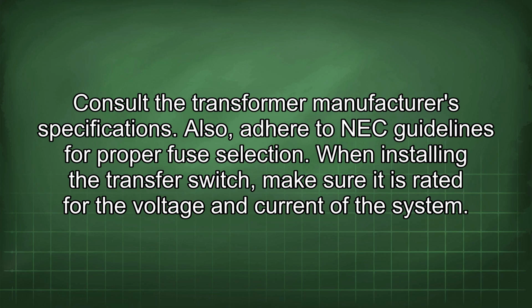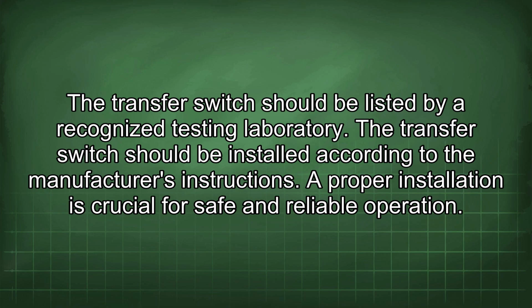When installing the transfer switch, make sure it is rated for the voltage and current of the system. The transfer switch should be listed by a recognized testing laboratory. The transfer switch should be installed according to the manufacturer's instructions. A proper installation is crucial for safe and reliable operation.